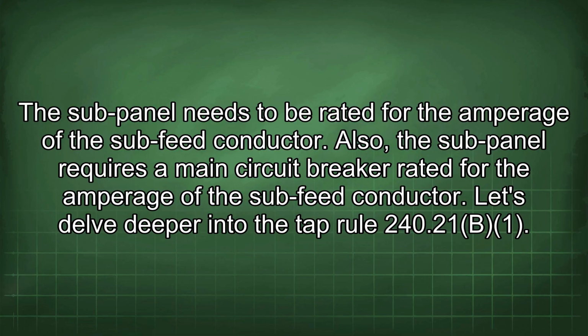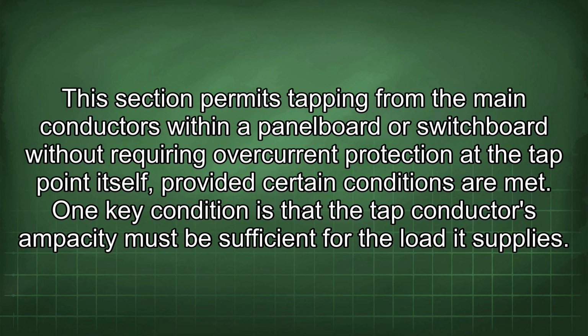Let's delve deeper into the TAP Rule 240.21(b). This section permits tapping from the main conductors within a panel board or switchboard without requiring overcurrent protection at the tap point itself, provided certain conditions are met.